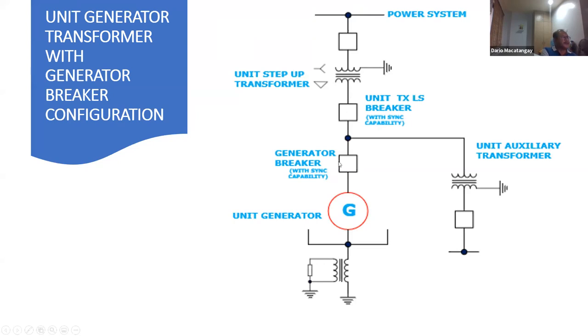So there's a large amount of power flowing through the transformer, okay? So when you have a fault in the transformer and this breaker opens, there's a big loss of load. When you have a huge loss of load, the generator and the turbine might go to instability, because before the breaker tripping, this generator is synchronized with the system.